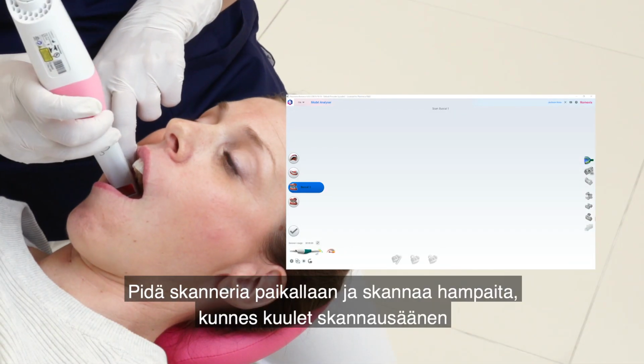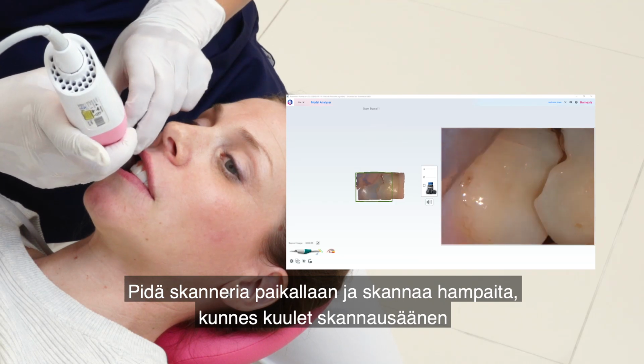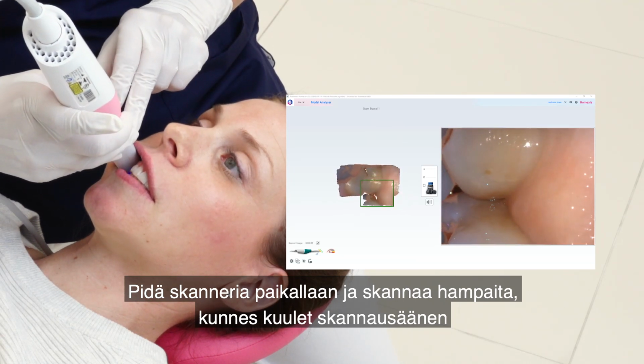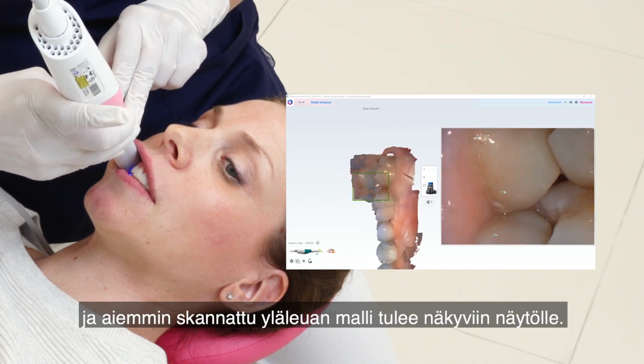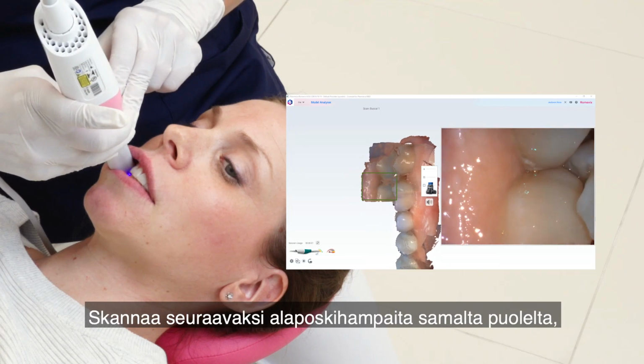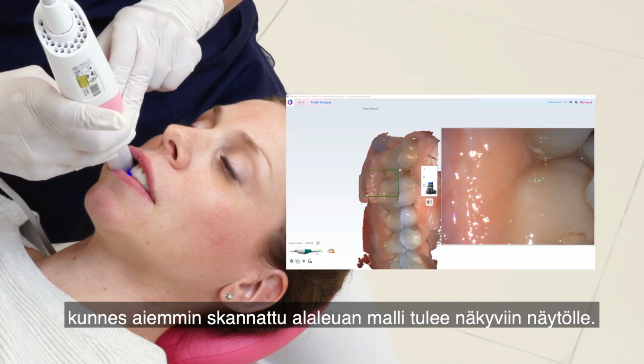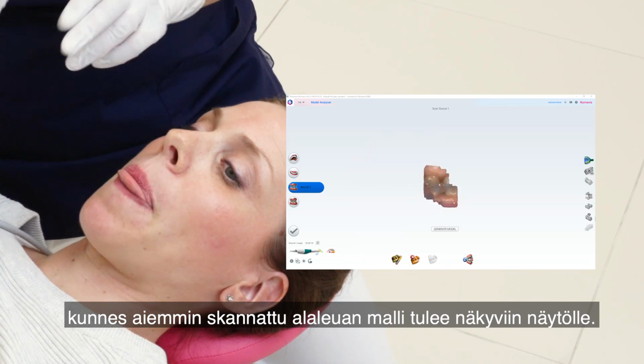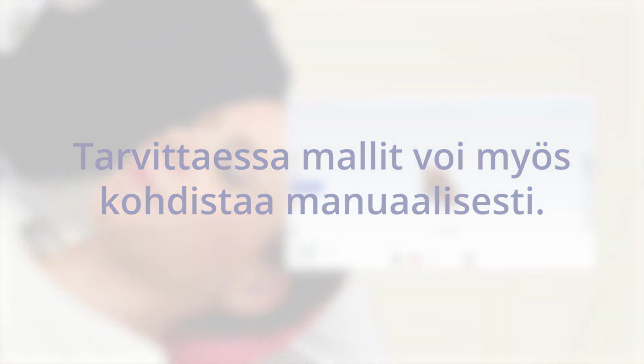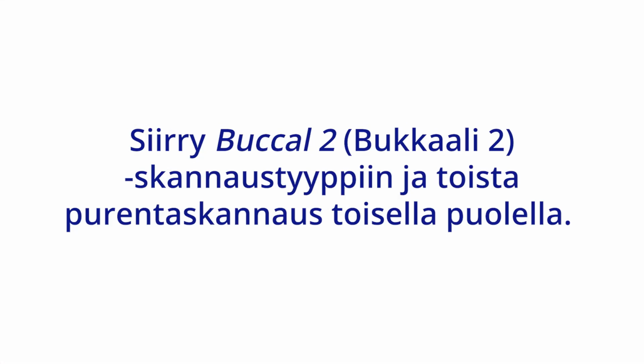Hold the scanner still and capture the teeth until you hear a sound signal and the previously scanned upper model appears on the screen. Next, capture the lower models on the same side until the previously scanned lower model appears. If necessary, the models can also be aligned manually. Move on to buccal 2 and repeat the buccal scan on the other side.